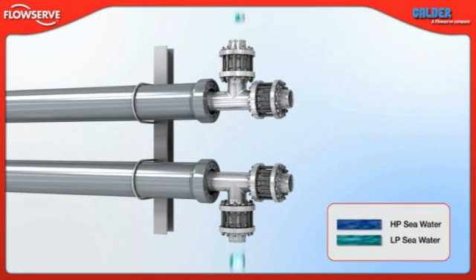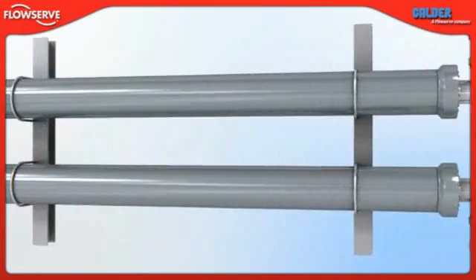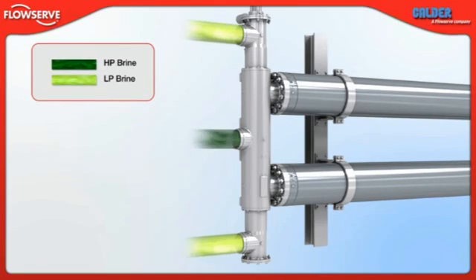Low pressure sea water from pre-treatment enters the DWEER through the inlet check valves and, once pressurized, exits the unit through the outlet check valves. Meanwhile, high pressure brine enters the DWEER through the middle port of the Linx valve and is expelled as low pressure brine through the top or bottom port.